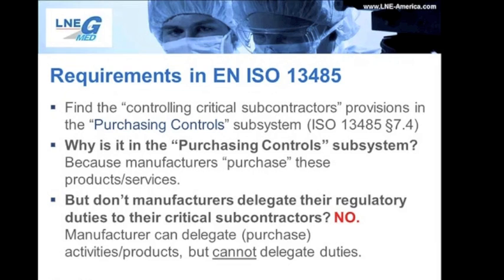Now, I should mention here, don't forget that even if you do subcontract manufacturing and sterilization and all of that, that's okay. But don't forget, you can't delegate away your regulatory responsibilities, and so your validation records do comprise part of your technical documentation. So that's just another way that manufacturers can show control, that they are controlling those critical subcontractors.